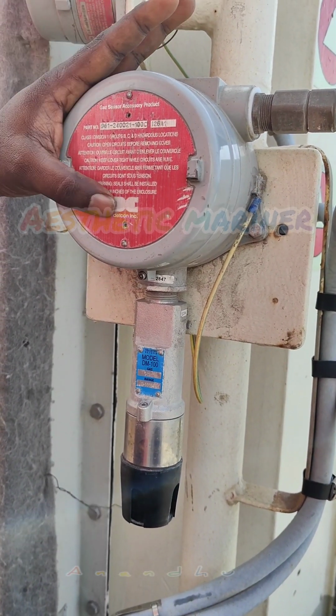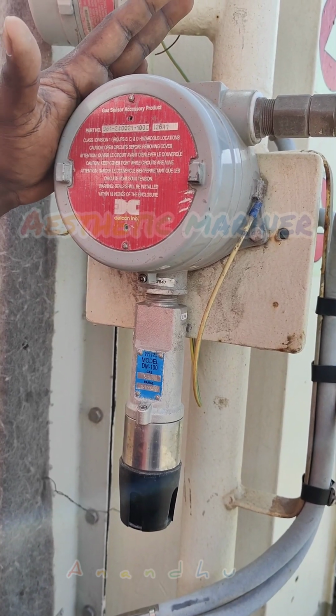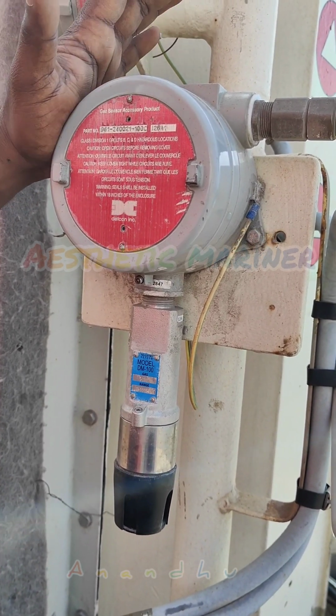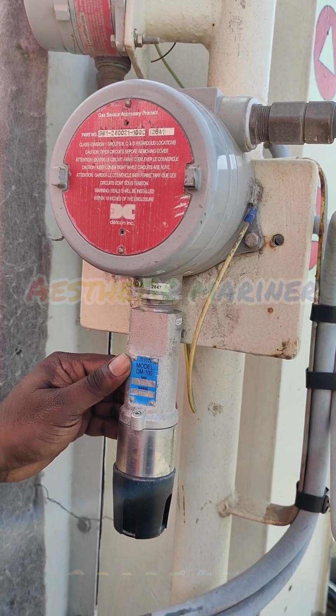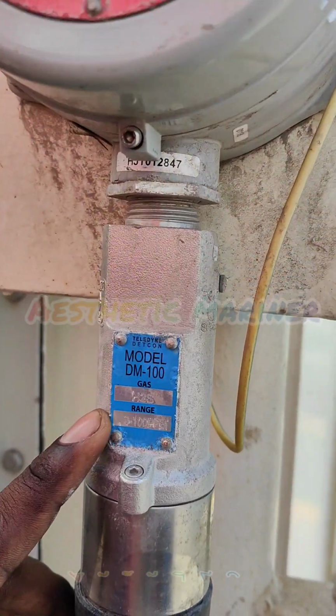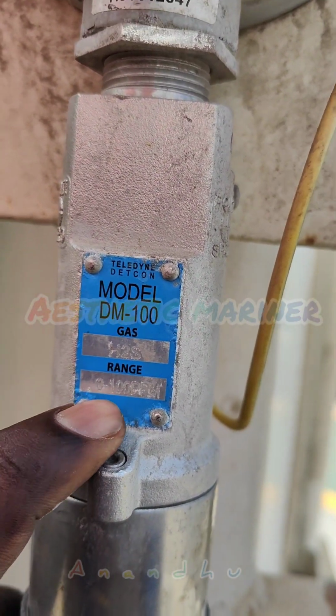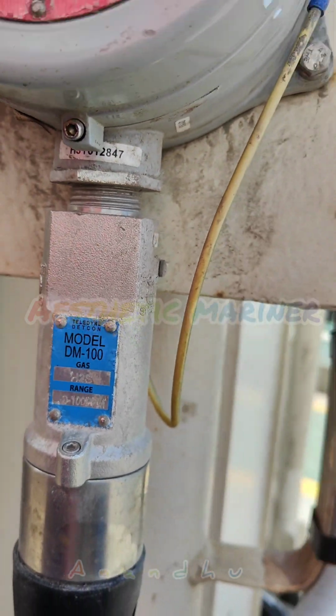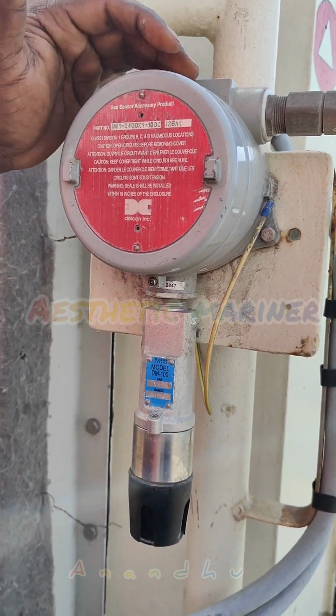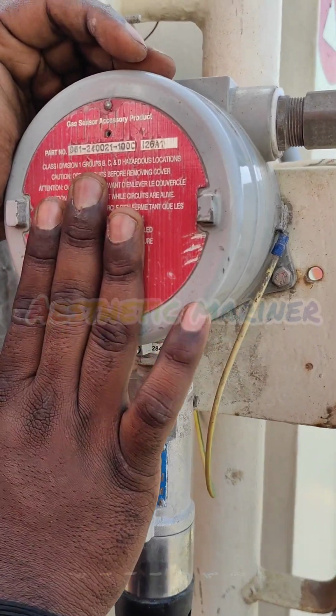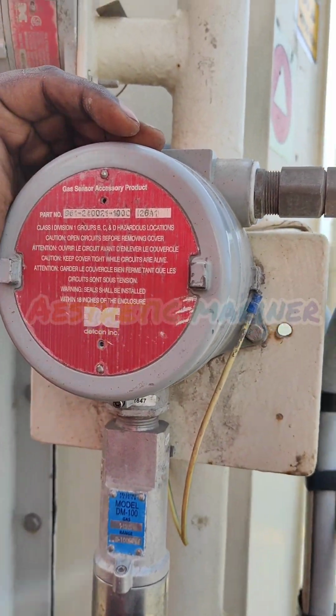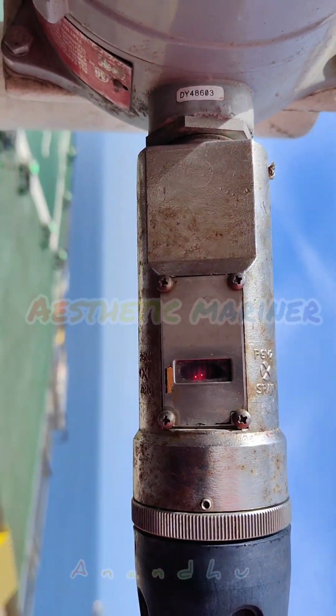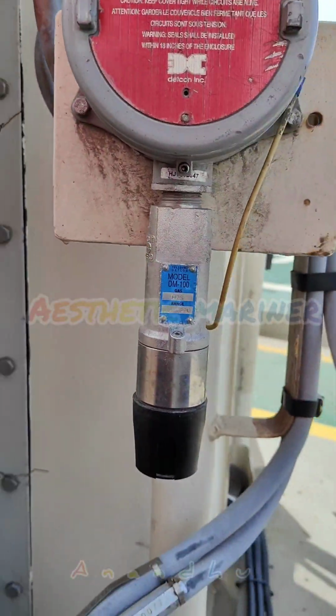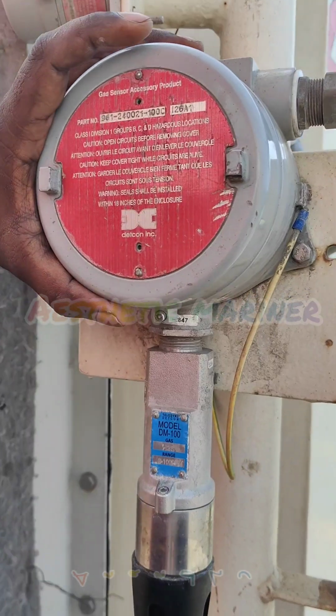Here we are going to see how to calibrate the Detcon DM100 model H2S sensor. This is the Detcon DM100 model H2S sensor. Here we can see the model DM100, H2S, and 0 to 100 ppm range. This DM100 model sensor has no display, so we need to do the calibration without a display. This is the display type Detcon sensor. Now we are going to see how to calibrate the non-display type model.